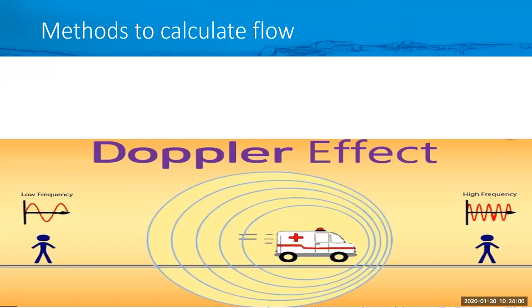With area velocity sensors like the ISCO in-pipe AV sensors, we use Doppler to read the velocity. We output a 500 kilohertz signal and read the frequency shift. The Doppler effect, as shown here with this ambulance, is that it transmits a sound, in our case a 500 kilohertz signal, and then it reads the frequency shift back to the sensor. As the sound or particles are moving towards the sensor, you're going to get a higher frequency, and as it moves away, it reads a lower frequency.